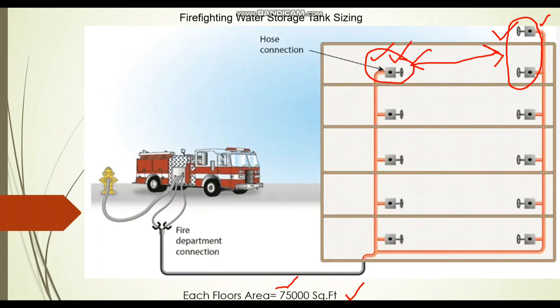In the same project, if the floor area is instead 82,000 square feet, there is no change for the last remote riser — still 500 GPM. But for the next standpipe, since the area exceeds 80,000 square feet, we must consider two landing valves instead of one. In that case the fire pump flow would be 1000 GPM.